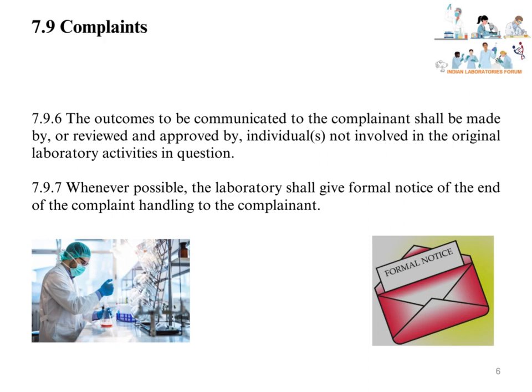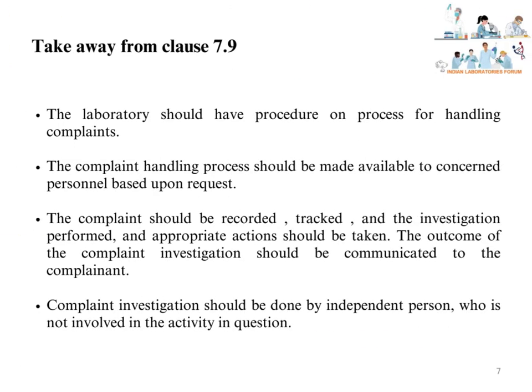Whenever possible, the laboratory shall give formal notice of the end of the complaint handling to the complainant. To summarize: the laboratory should have a procedure for handling complaints; the complaint handling process should be made available to concerned personnel on request; complaints should be recorded, tracked, and investigated with appropriate actions taken; the outcome should be communicated to the complainant; and the investigation should be done by an independent person not involved in the activity in question.